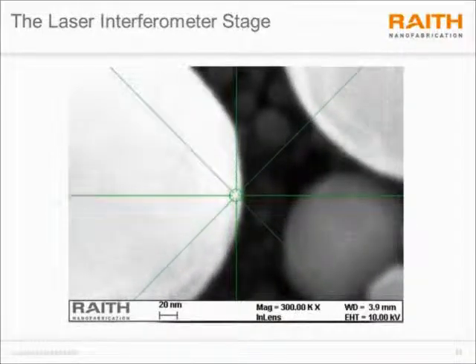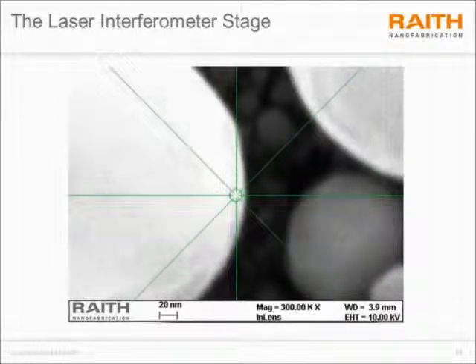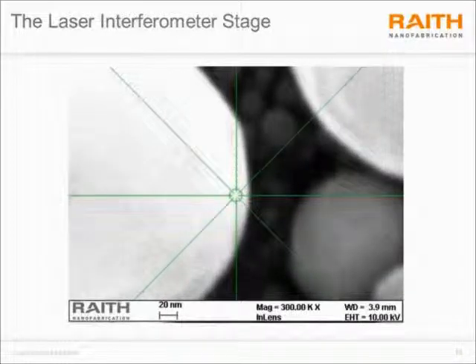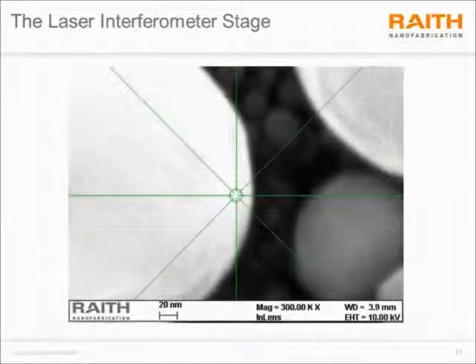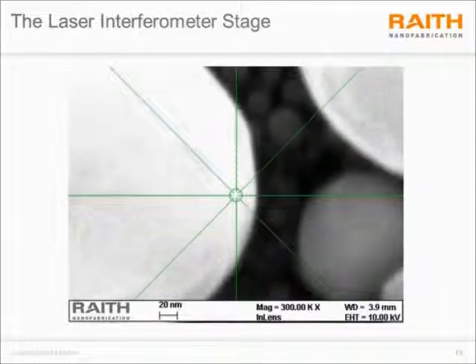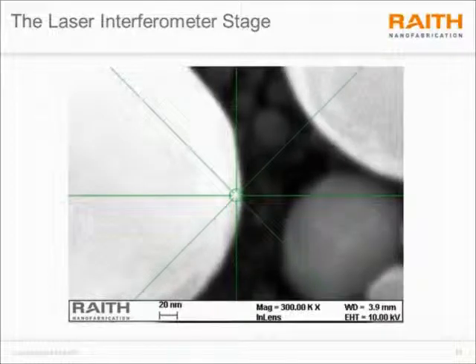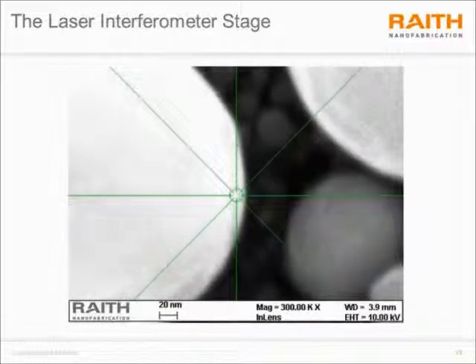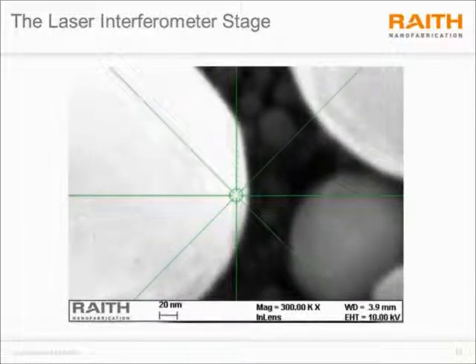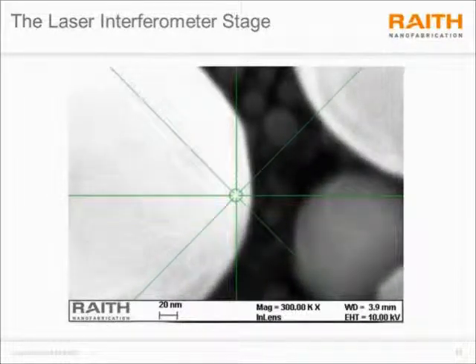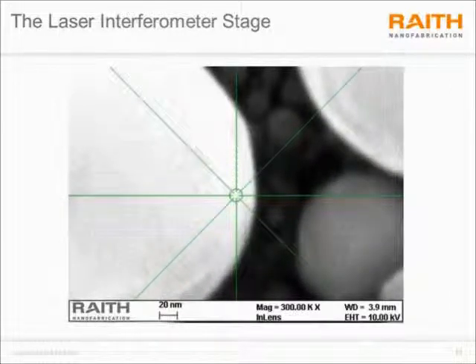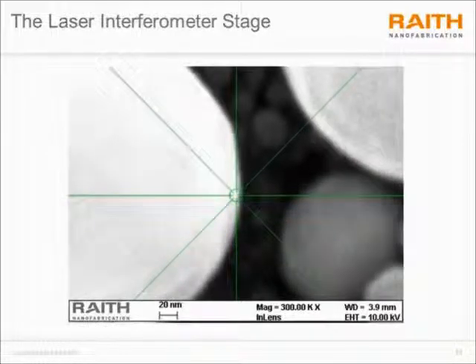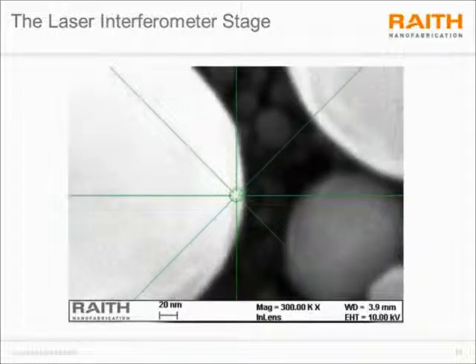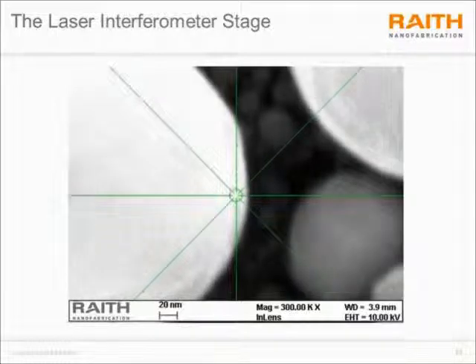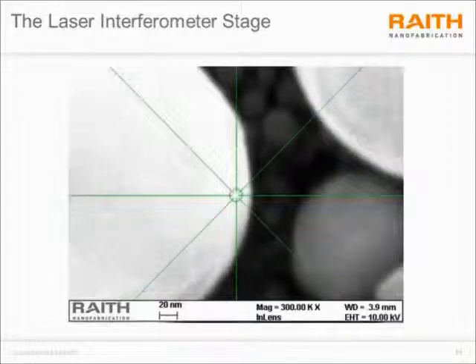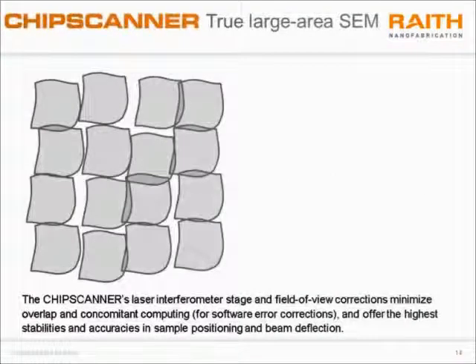So having a closer look now at the laser interferometer stage, here we have a 300,000x magnification image video being recorded that shows a tin on carbon sample. This tin ball is being moved to the right by the user depressing the joystick on the chip scanner. And essentially, what you can see here is very precise and stable motion underneath the field of view of the scanning electron microscope. And anybody who is used to operating scanning electron microscopes always finds that when you press the joystick at this magnification, this feature would be lost, completely lost, and would never be found again. But with the laser interferometer stage, this feature is just slowly moved to the right. And this capability allows us to map out the errors in the field of view.